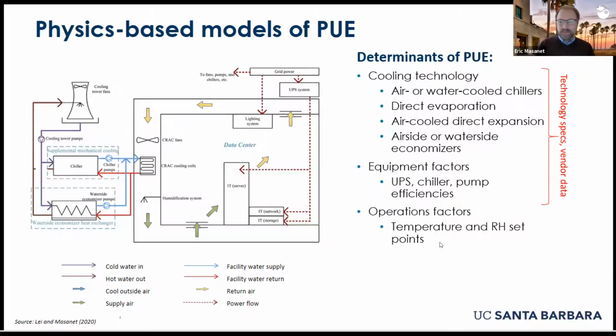We also have to have some idea of how the cooling system is operated. So a really important factor is the set points - what temperature and relative humidity are allowed inside the data center. The hotter we can run data centers, the less cooling we need. Some of the really cutting edge data centers run really hot, at 85, 90 degrees Fahrenheit, and at those temperatures we require very little cooling.